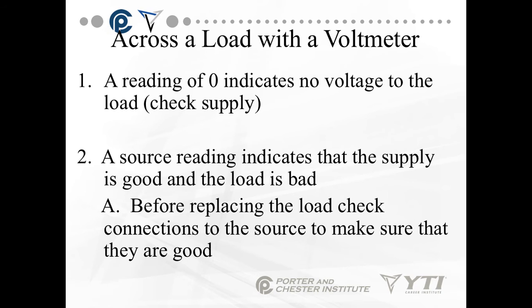If you check across a load with a voltmeter, a reading of zero indicates no voltage to the load, so you have to find out from the supply side why you're not getting voltage. A source reading indicates the supply is good and the load is bad.